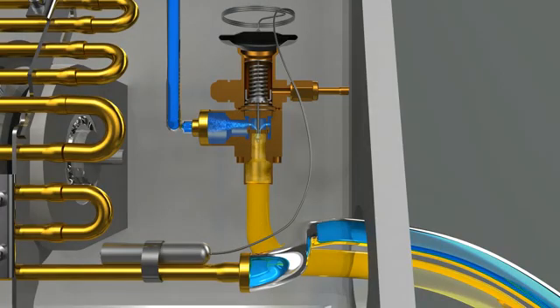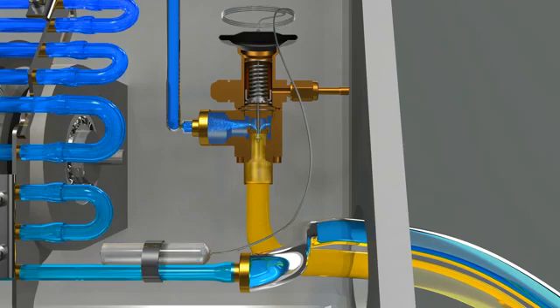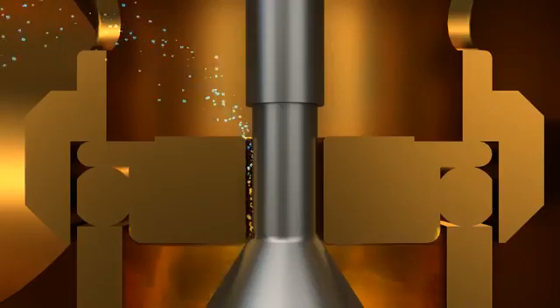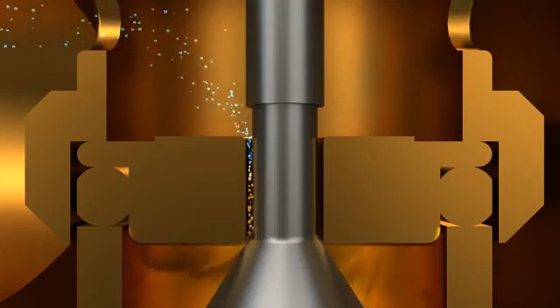The expansion valve is connected to a temperature sensing bulb that detects heat. The sensing bulb is installed on the exit of an evaporator and detects temperature. Inside the bulb is fluid sensitive to temperature changes, and as the temperature at the exit of an evaporator rises, the gas pressure rises, which in turn presses on a spring to send more refrigerant to the evaporator.